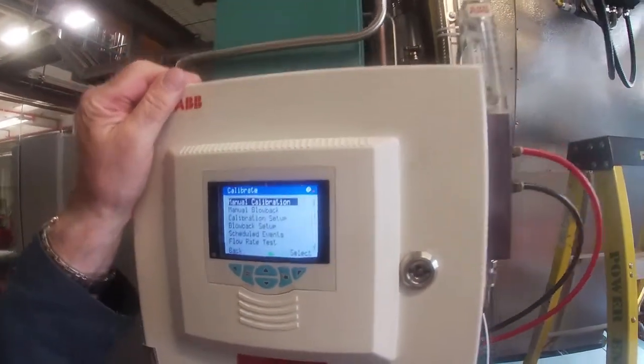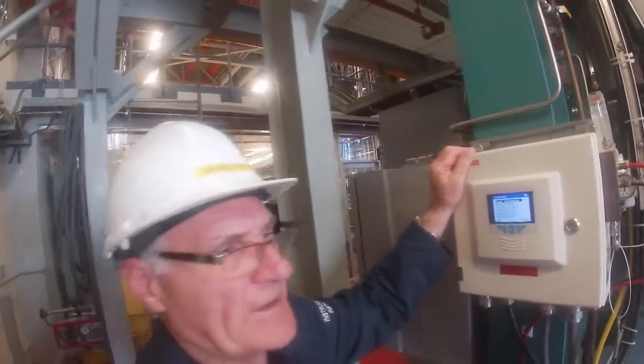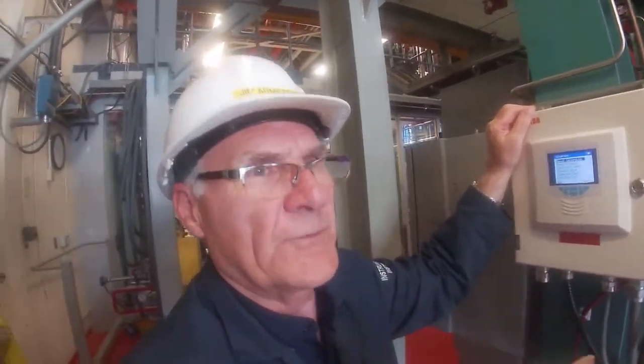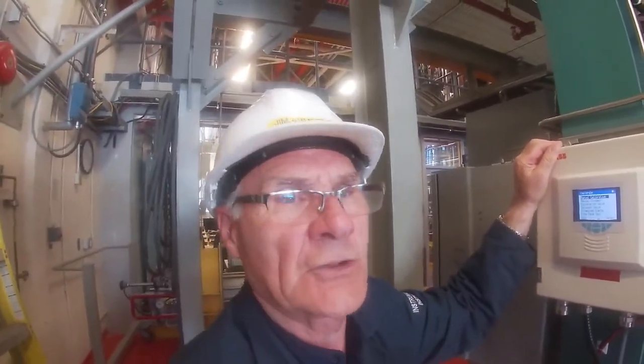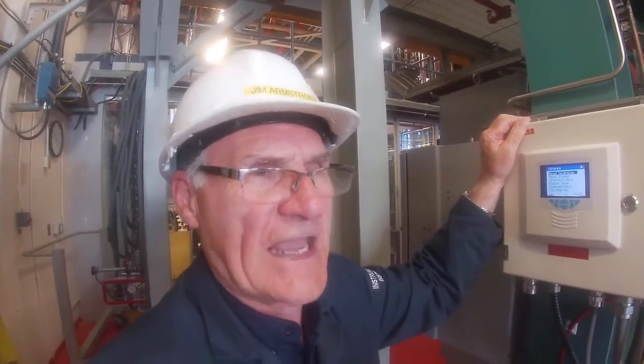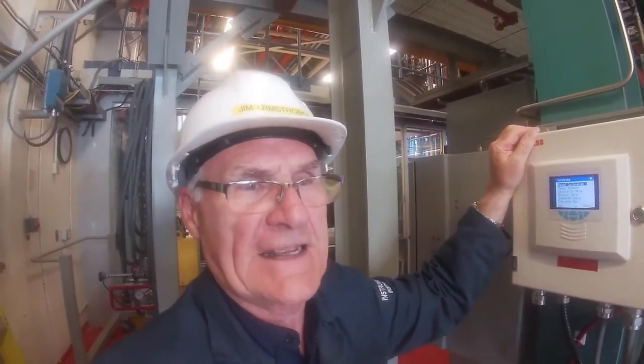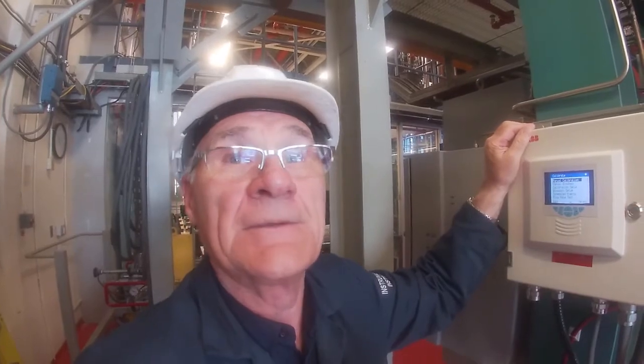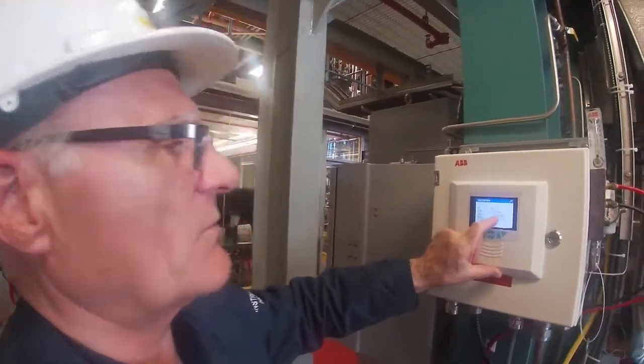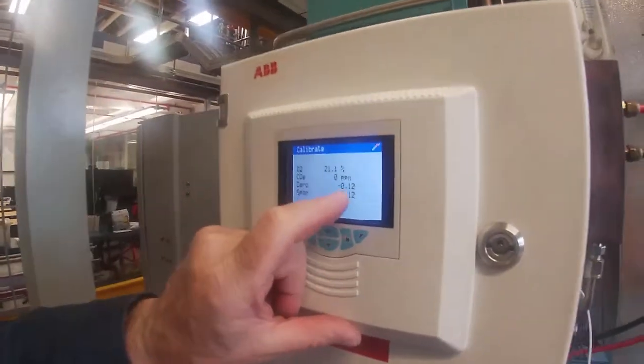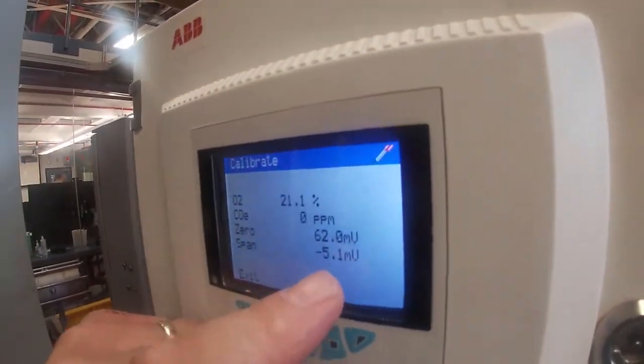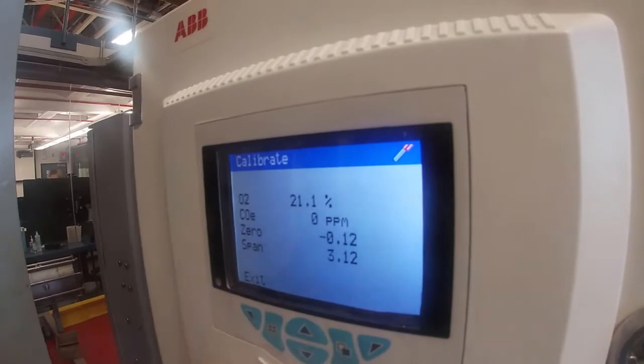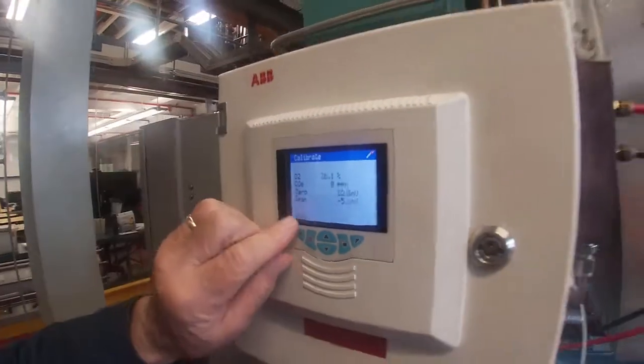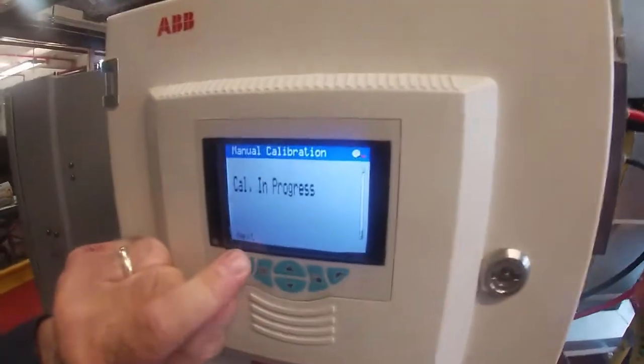Now typically what I do, and we will do this, we'll turn the video off for this, but I go through and repeat it. And I want to see if the values have actually changed from one calibration to the next over just a 5-minute period. Okay, so we cut it off. So the calibration worked out reasonably well. You can see these numbers have moved a little bit from the last calibration we did a few minutes ago, but it's an insignificant amount. So I'm going to exit back out of here.